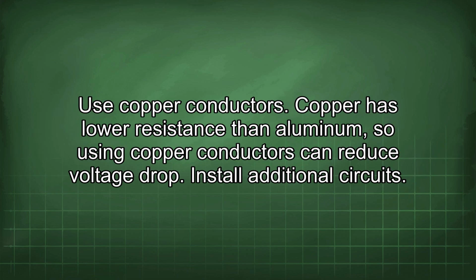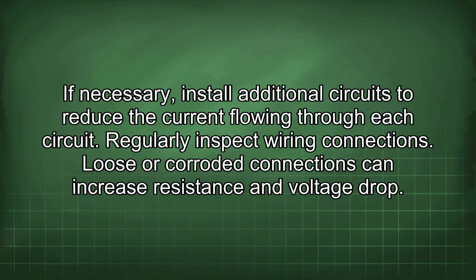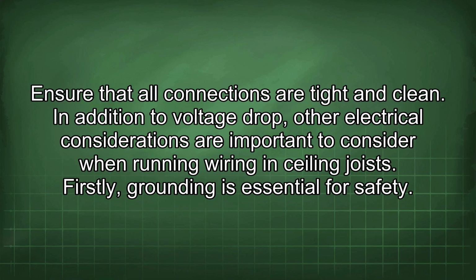Use copper conductors. Copper has lower resistance than aluminum, so using copper conductors can reduce voltage drop. Install additional circuits. If necessary, install additional circuits to reduce the current flowing through each circuit. Regularly inspect wiring connections. Loose or corroded connections can increase resistance and voltage drop. Ensure that all connections are tight and clean.